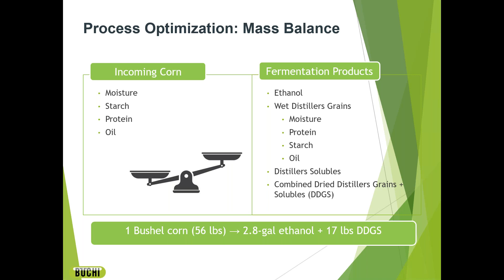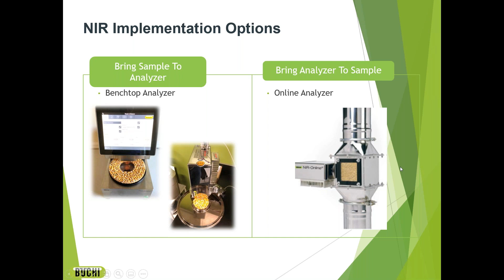So how do we implement this? There are different ways to do that. If you had a benchtop analyzer, the conventional form of analysis, it would require bringing the sample to the analyzer. The alternative is to bring the analyzer to the sample. Here we show a particular type of conveyor full of corn, with an analyzer directly coupled into that production line. These are the basic options, but let's think about this in terms of scenarios.